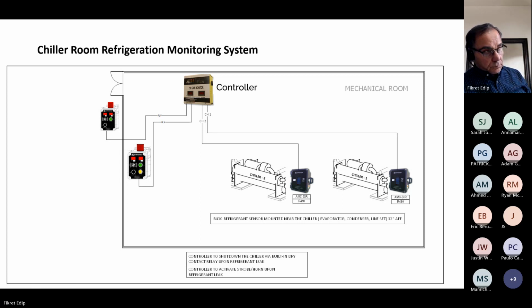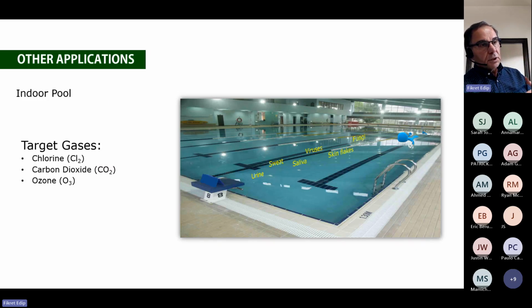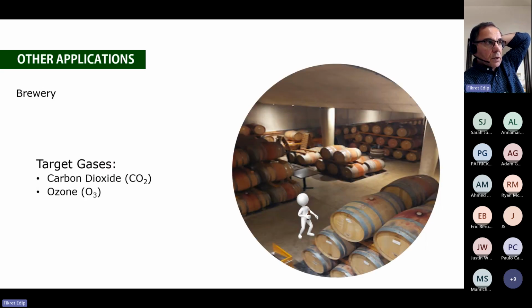Furthermore, if your mechanical room has more than one entrance, you put a strobe horn at each entrance in the mechanical room. So these are things you need to pay attention to when you are designing a chiller room detection. Swimming pool, you get all that in the water, as you can see. The target gases: chlorine, carbon dioxide, and ozone.